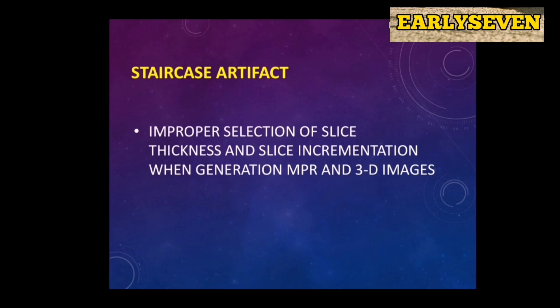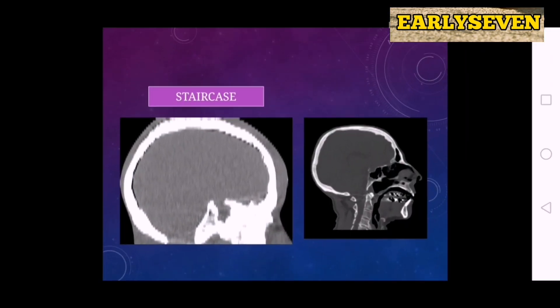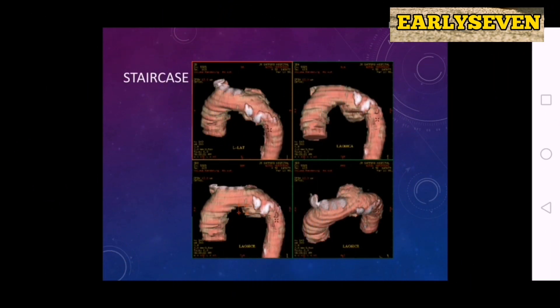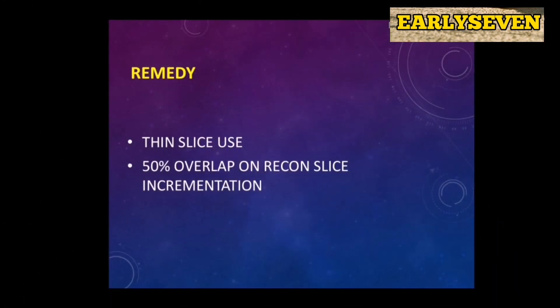Lastly, the staircase artifact results from improper selection of slice thickness and slice incrementation when generating MPR or multi-planar reconstruction and 3D images. The remedy for staircase artifact includes the use of thin slices and 50% overlap on reconstruction slice incrementation.